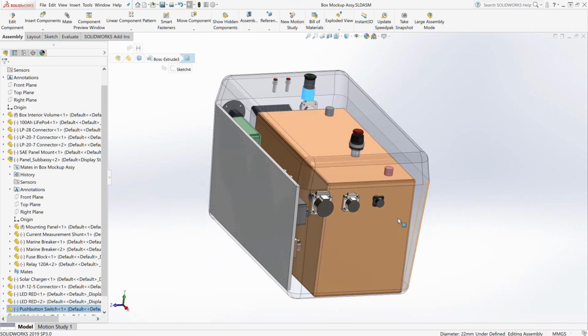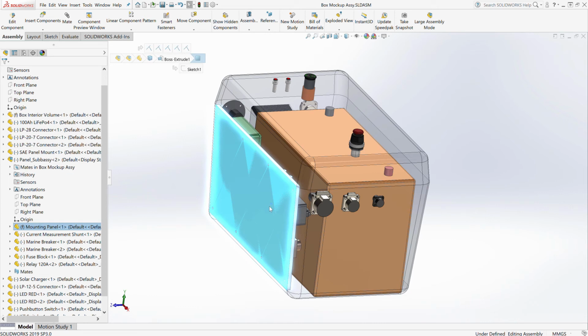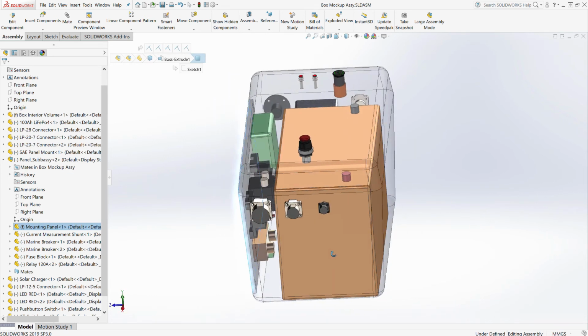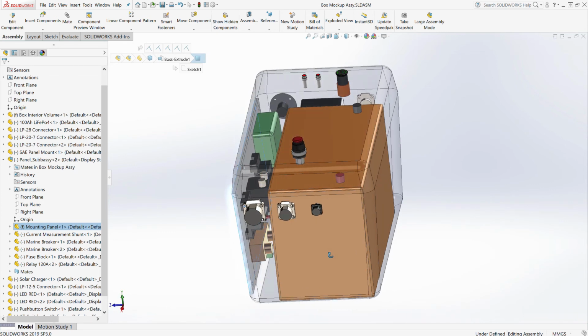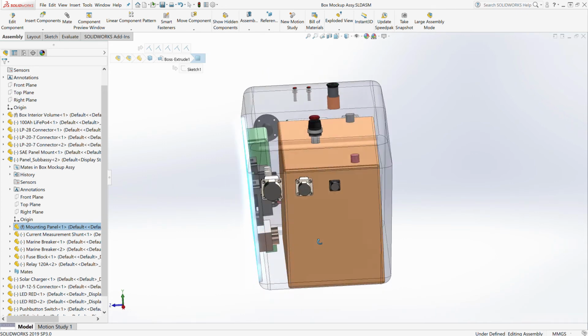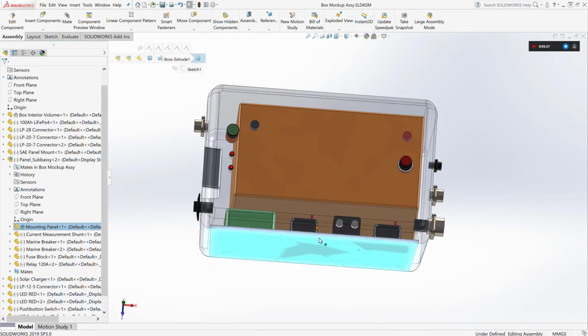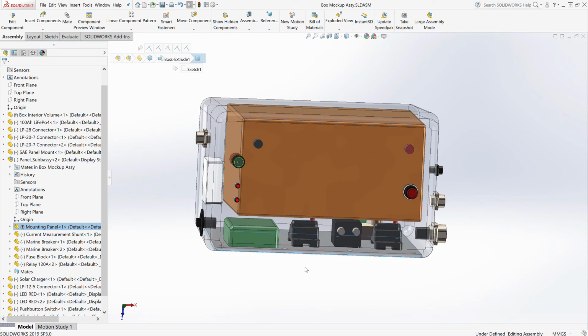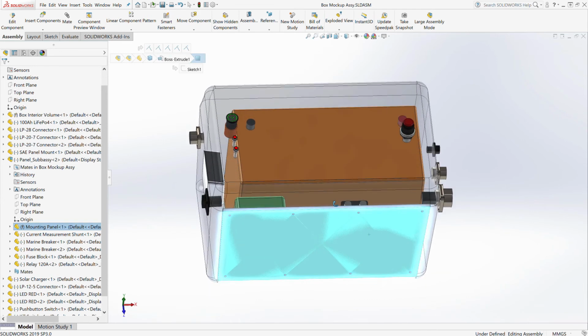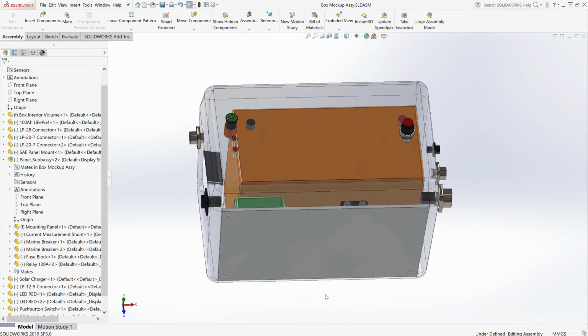One component I haven't talked about is this panel. It's a quarter-inch thick HDPE plastic panel that I've milled to attach these components to. The purpose is that these components collectively require a very large number of mounting holes. If I bolt them to a panel and then bolt the panel to the enclosure, I greatly reduce the number of mounting holes and therefore the number of potential water ingress points.